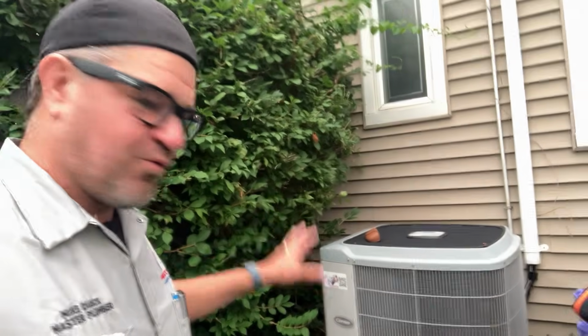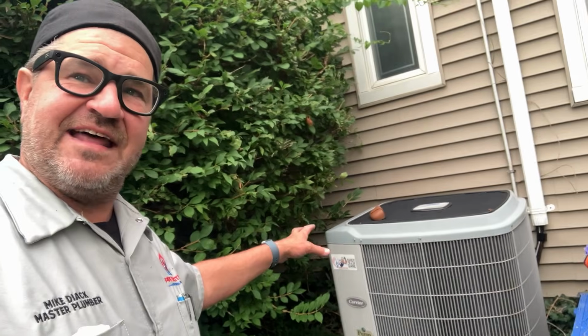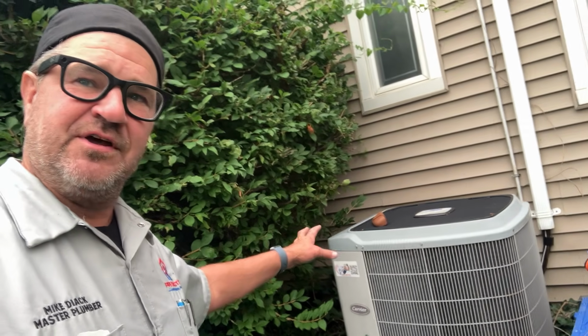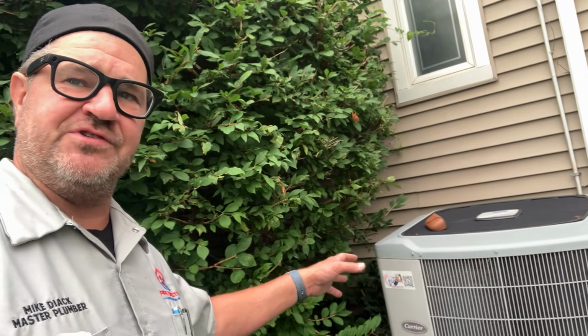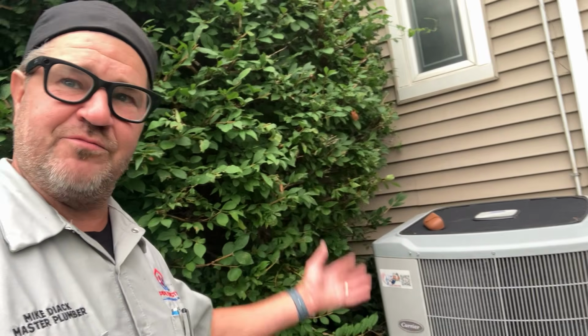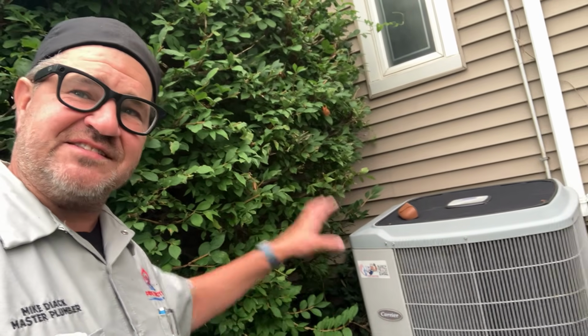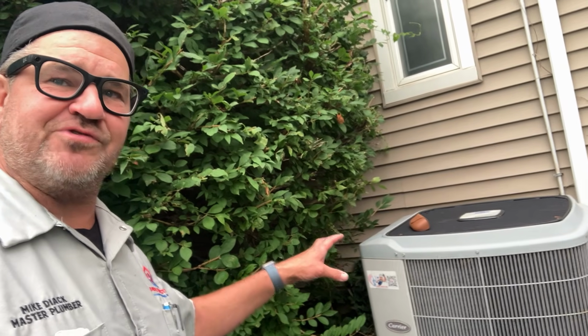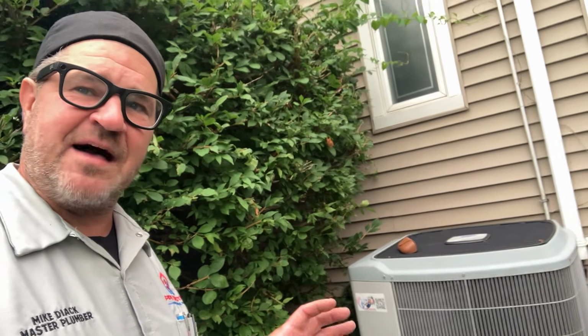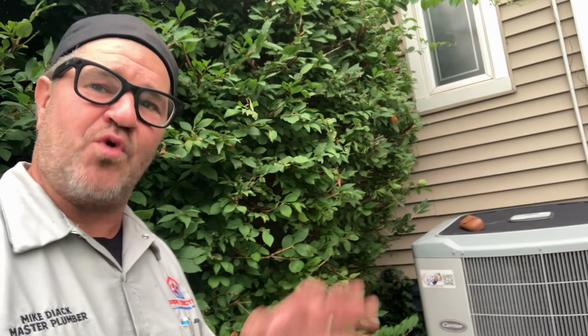Let's briefly go over what I just did as a tech tip on how I save time. Before we disconnect this old outdoor unit, we perform what is called a pump down. Instead of recovering all the refrigerant into a recovery cylinder by means of a recovery machine, we use the system's own compressor to move the refrigerant into the outdoor condenser and isolate it there. On a system that's still operational like this one, that's a huge time saver. Depending on the size of the system and the amount of refrigerant, this could save us anywhere from 20 to 45 minutes compared to traditional recovery.